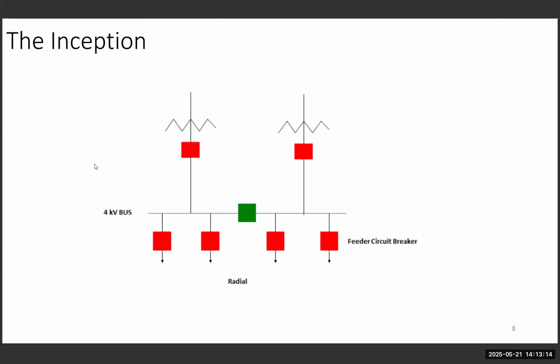So let's start right away, starting from the basics. What I like about substations is that you can never say you've seen every design. Even when you say this is known as a straight bus design, you see the horizontal bus - you've got two transformers, two lines feeding the bus, and from the bus you've got four circuits connected below. There's a normally open point, which is that green breaker you see here.